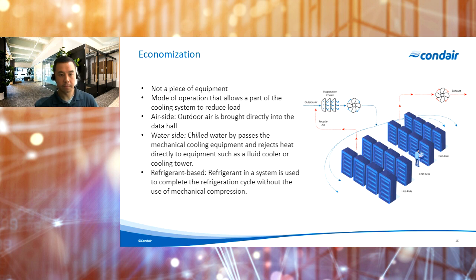Now we can look a little bit more into how economization is accomplished. To be clear, economization is not a piece of equipment per se. It's a mode of operation that allows part of your cooling system, such as a chiller, to shut down or reduce load, saving resources. There are a number of different ways that economization can be accomplished. The three main ones that we'll go over are air side, water side, and refrigerant-based.